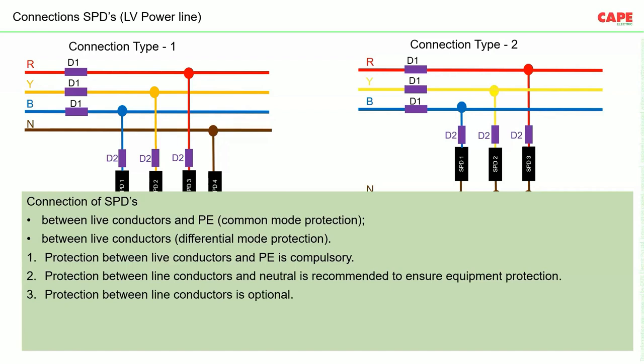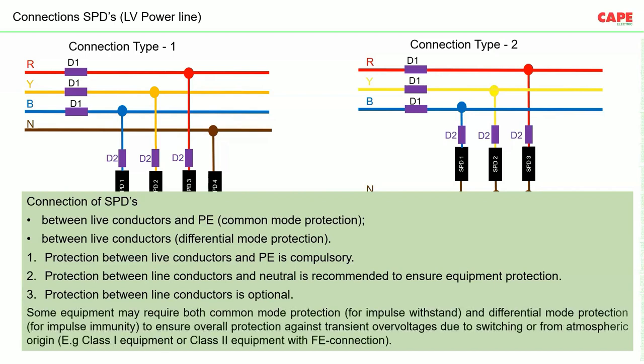Protection between line conductors is optional. Some equipment may require both common mode protection for impulse withstand and differential mode protection for impulse immunity, to ensure overall protection against transient voltage due to switching or from atmospheric origin — for example, class 1 equipment or class 2 equipment with FE connection.